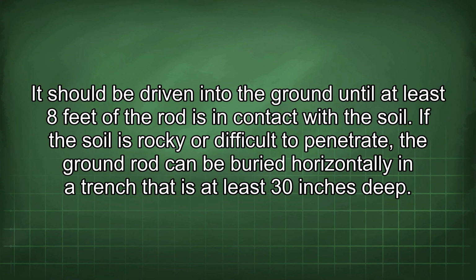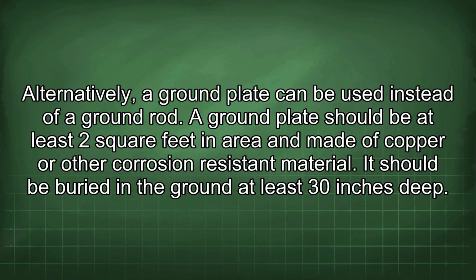If the soil is rocky or difficult to penetrate, the ground rod can be buried horizontally in a trench that is at least 30 inches deep. Alternatively, a ground plate can be used instead of a ground rod. A ground plate should be at least 2 square feet in area and made of copper or other corrosion-resistant material. It should be buried in the ground at least 30 inches deep.